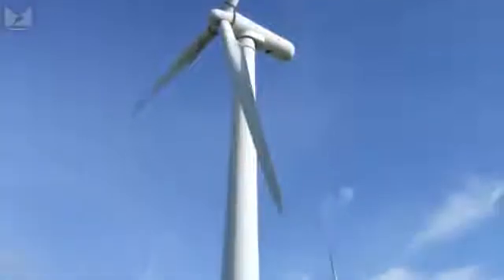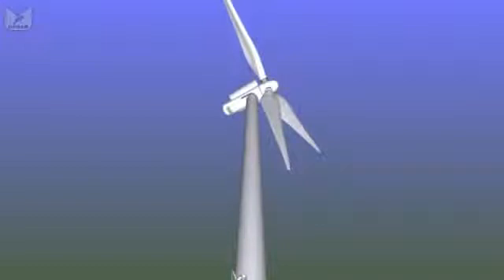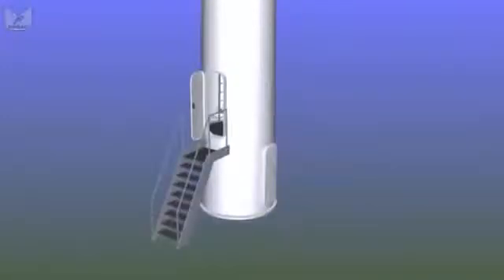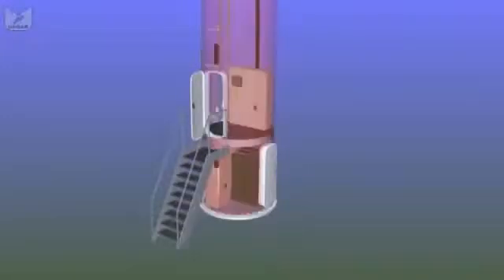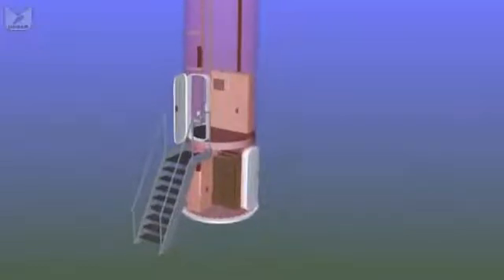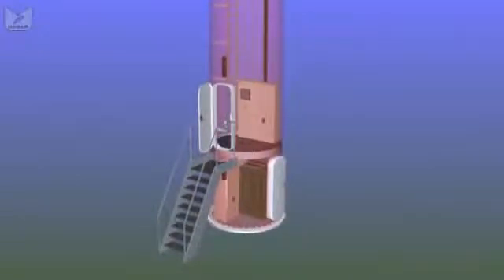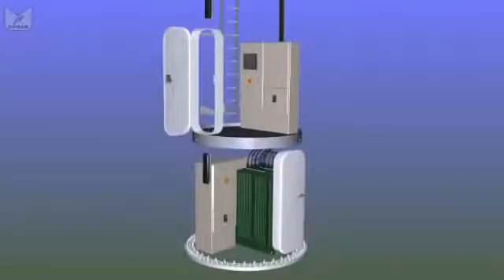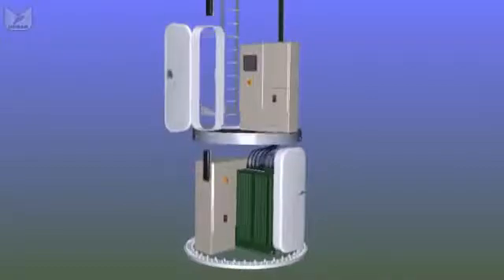Apart from physical scale, they are arranged a bit differently, so let's start by looking at a typical sub-megawatt model. Turbines of this type are typically 25 to 45 meters tall, and at the base you will often find two doors. The lower door takes you into a secured compartment where we have a high voltage step-up transformer. The generator at the top of the turbine is producing about 690 volts, and this transformer converts that into several thousand volts to send it more efficiently to the substation. The main entrance to the turbine is at first floor level, and there we find a control cabinet, the base of a ladder, or a series of ladders.